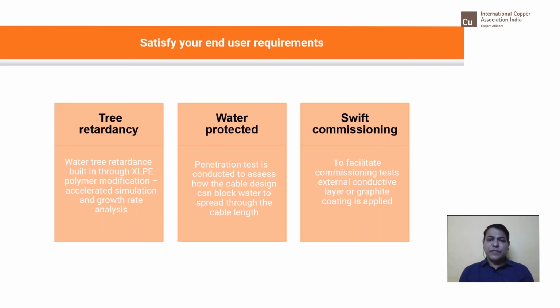And the third one is the external conducting layer on the outer sheath, to check the integrity of the outer sheath during the commissioning, because any pinhole or a small damage on the cable sheath can let water come into the cable and it can destroy the cable within no time. So it is very important to check the integrity of the sheath. The voltage is applied between the conducting layer and the armor to confirm that there are no pinholes or any damage to the sheath.